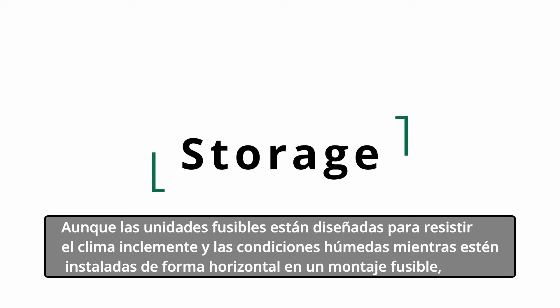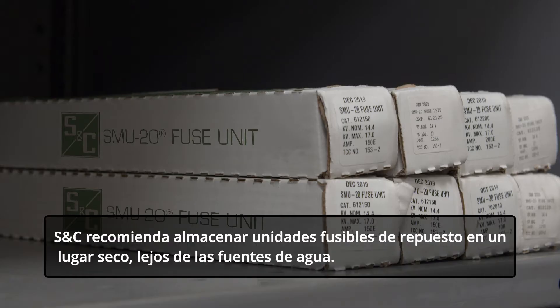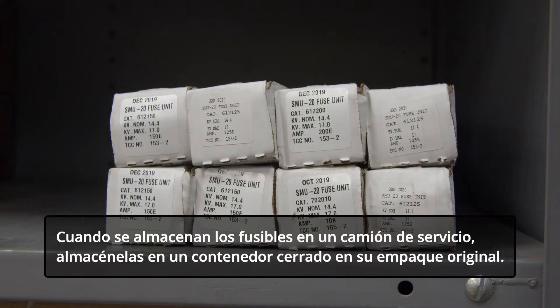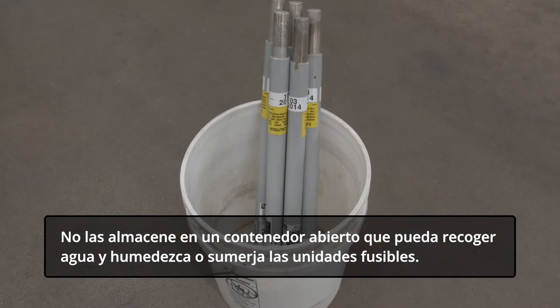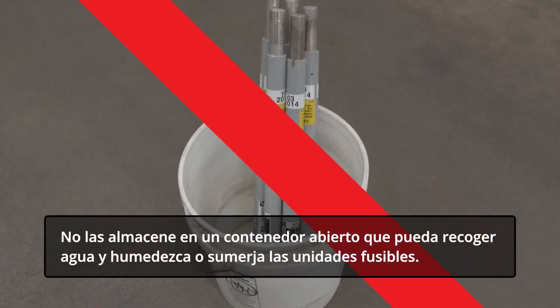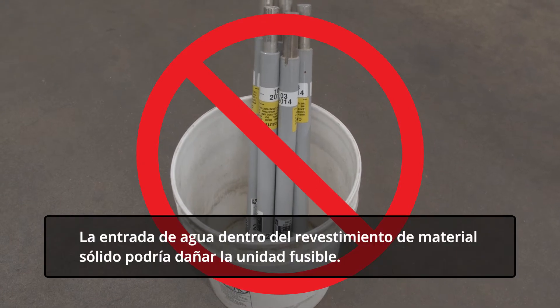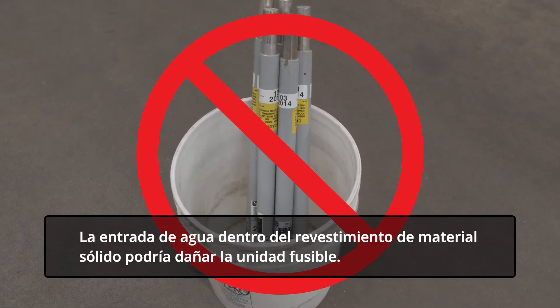Though fuse units are designed to withstand inclement weather and wet conditions while installed upright in a fuse mounting, S&C recommends storing replacement fuse units in a dry place, away from sources of water. When storing fuses on a service truck, store them in a closed container in the original packaging. Do not store them in an open container that may collect water and soak or submerge the fuse unit. Water entry into the solid material lining could damage the fuse unit.